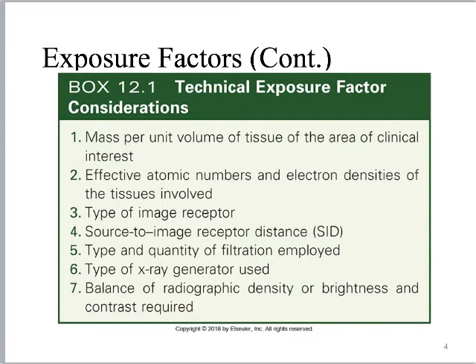There has been discussion in the literature about shooting certain exams at an even greater SID beyond the 72 inches we generally use. We continue to ask how we can produce x-rays with decreased patient dose — could we further increase the SID? The type and quantity of filtration employed can largely decrease patient skin dose. Total filtration includes both inherent and added filtration. Added filtration slides in between the tube and the collimator and is managed by the health physicist.